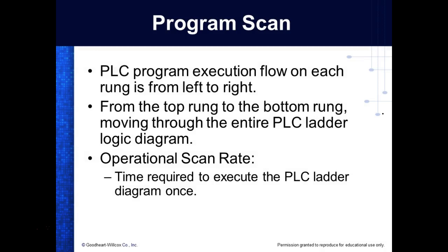The way the PLC works is it constantly scans the program. What it does is it hits a rung, starts at rung 0, scans the inputs, runs the logic, updates the output. And then it drops down to the next rung. So the more rungs you have, the more scan time it takes.